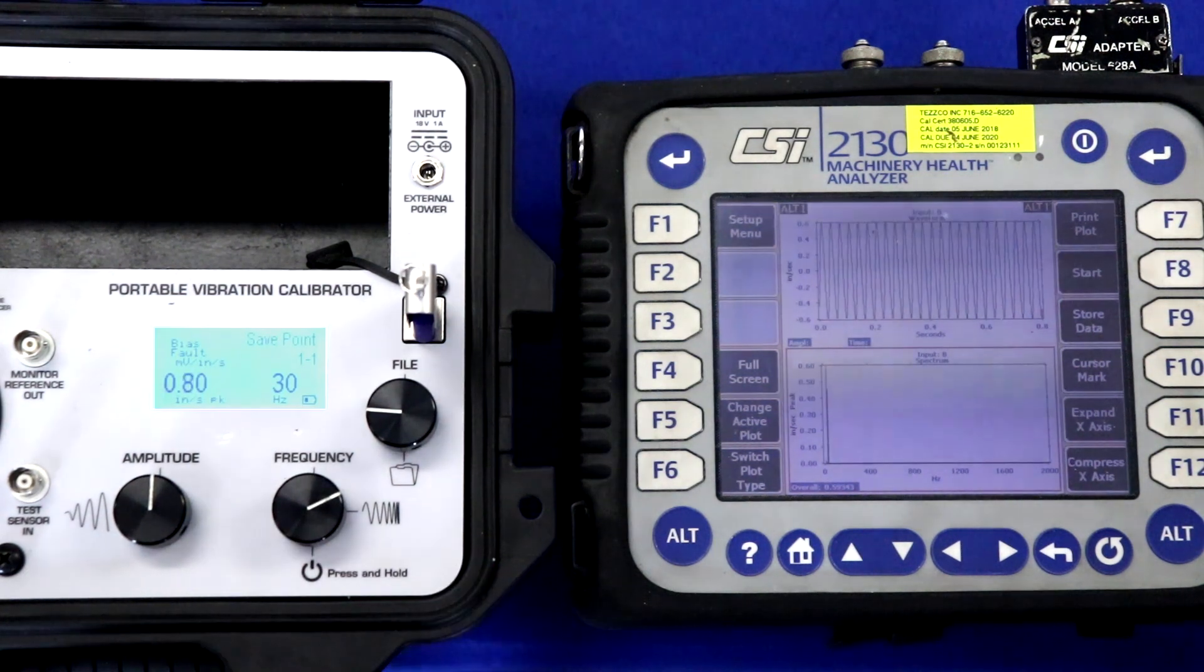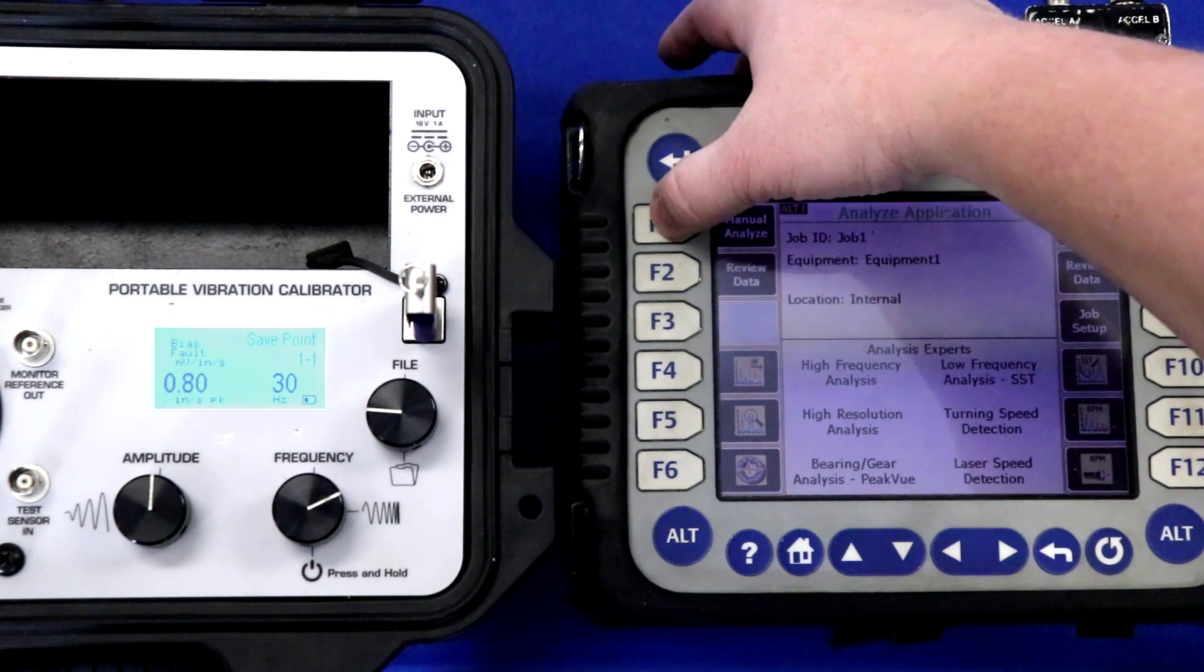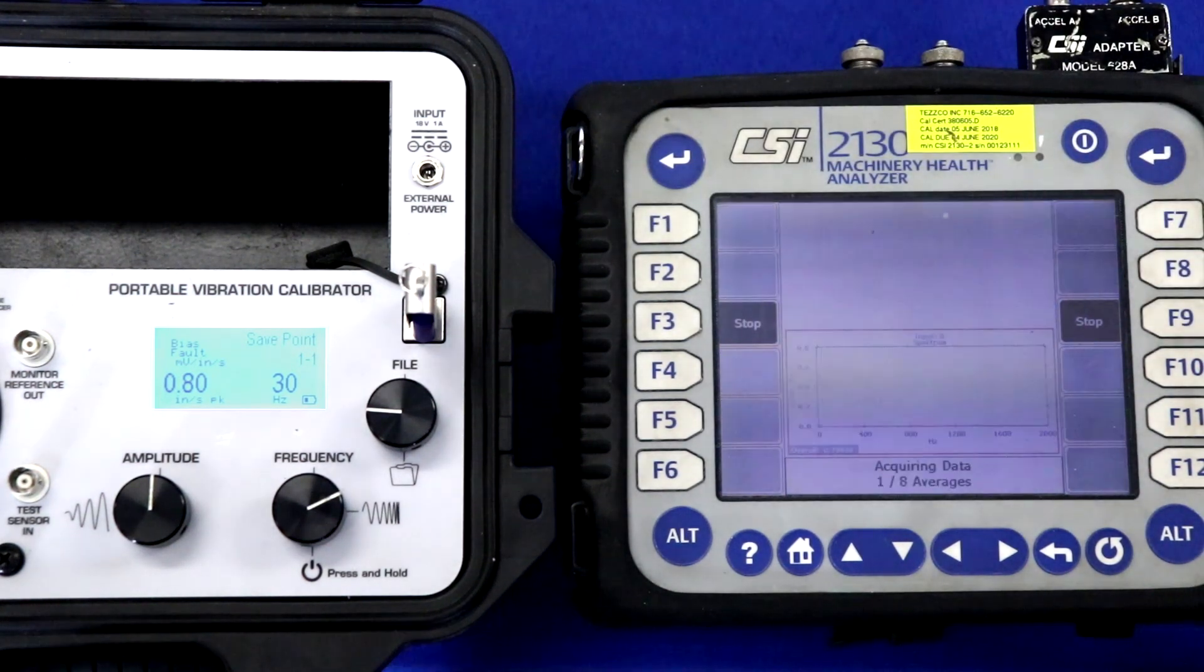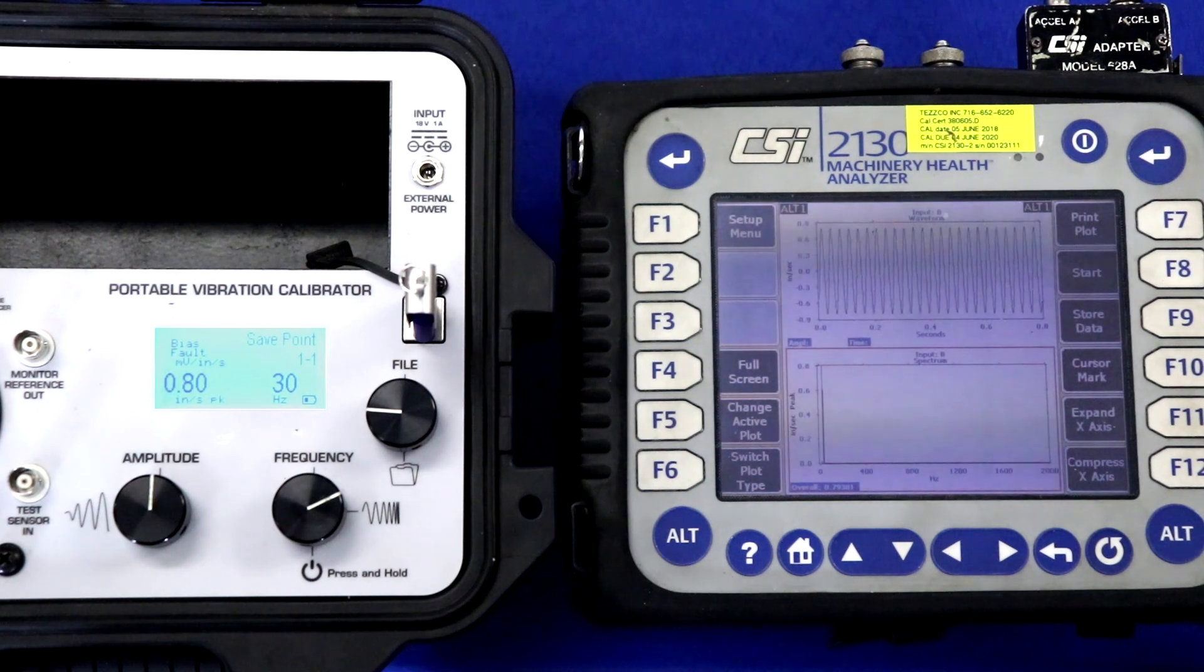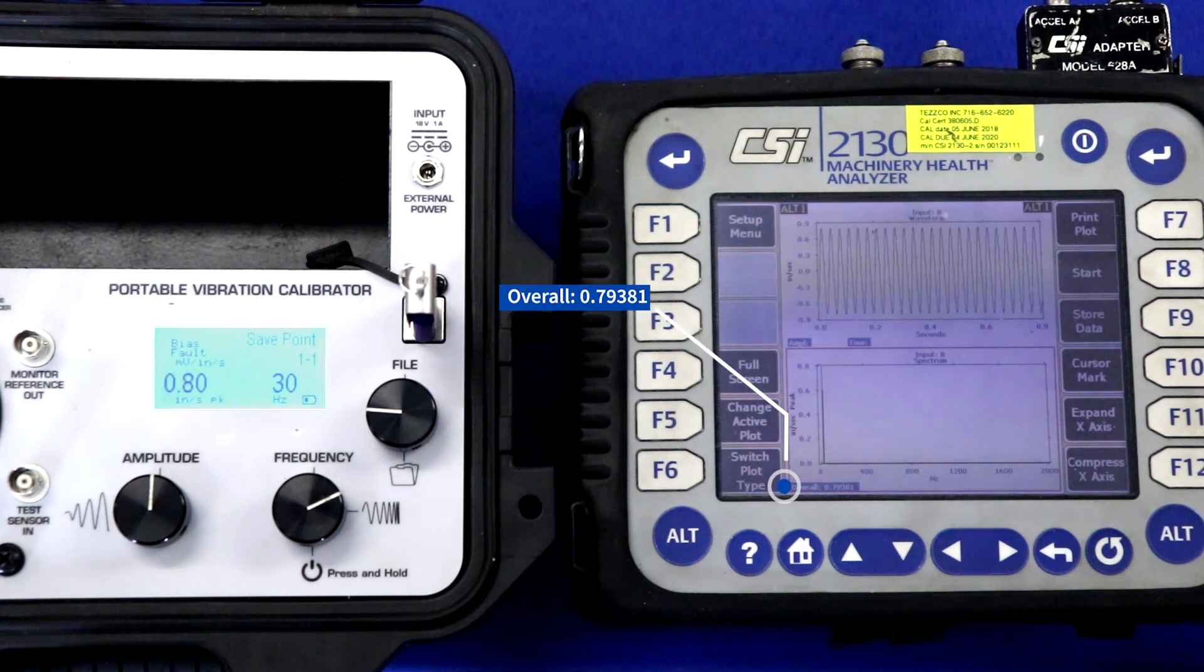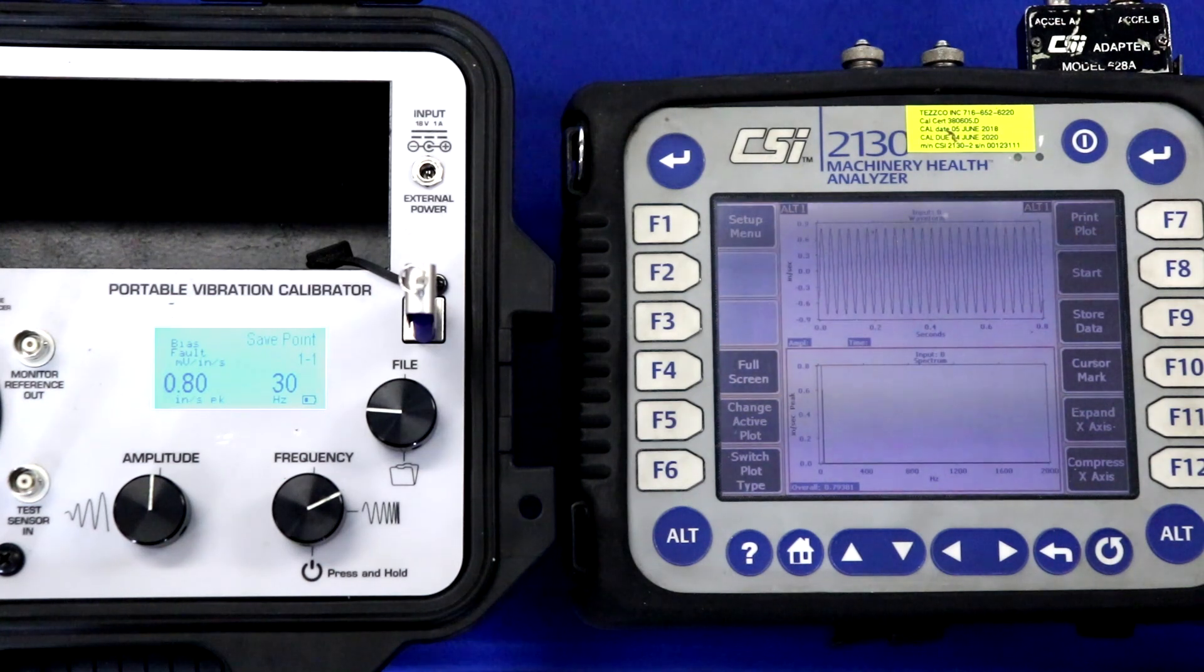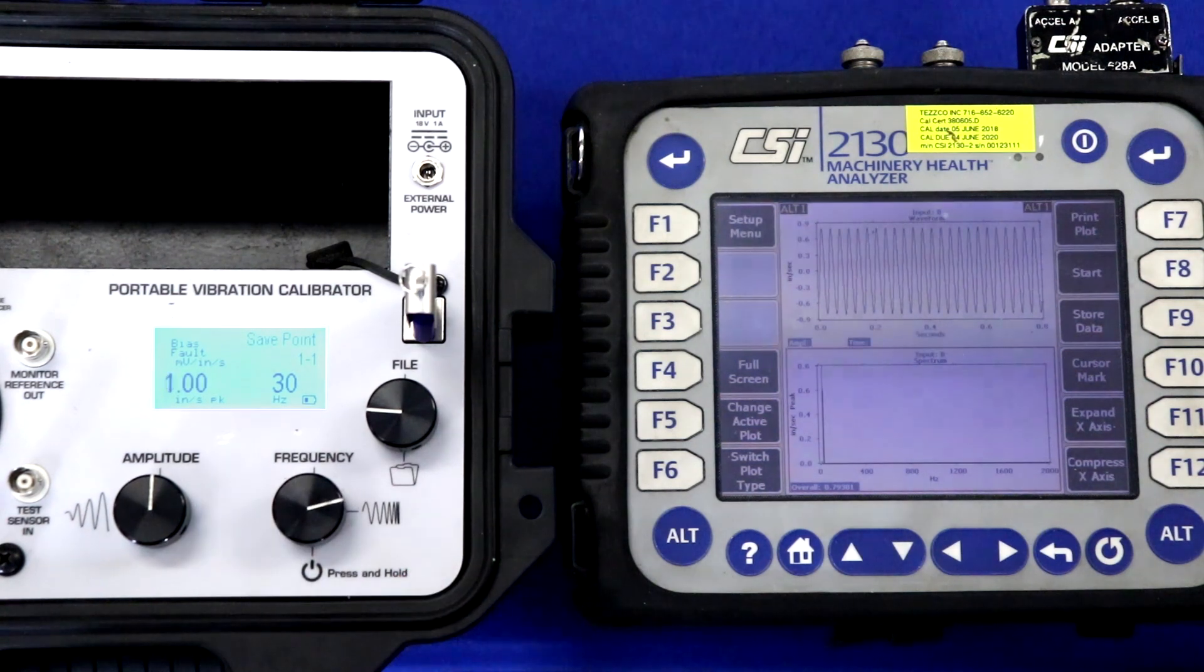Moving on to 0.8 inches per second peak, we acquire our eight averages, and you can see that the overall vibration is 0.793 inches per second peak. So again, just slightly lower than the calibrated value of 0.8 inches per second peak.